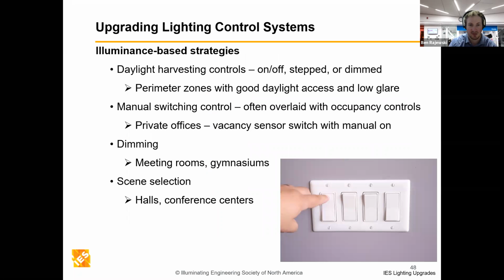With illuminance-based strategies, the biggest one with LEDs is dimming. You're able to dim almost all LEDs now relatively easily, giving people a level of control they didn't normally have with fluorescents. With fluorescents you often just had partial light level changes by turning off sections of fixtures or every other fixture, dimming by turning things off instead of getting a natural dimming effect from turning all the lights down at the same time.